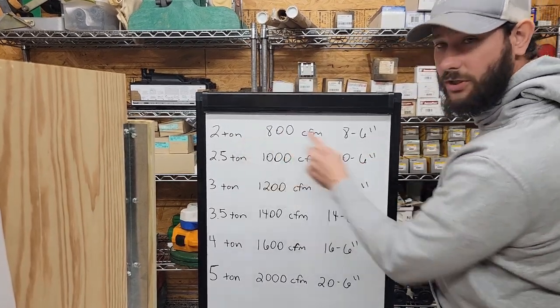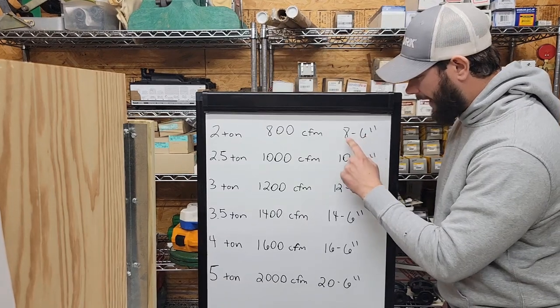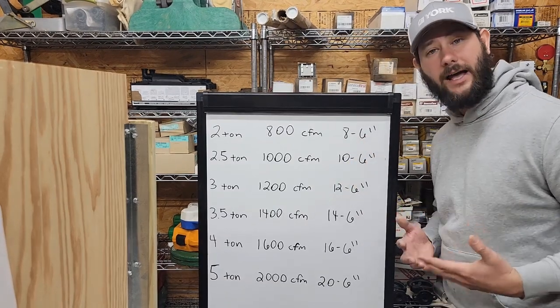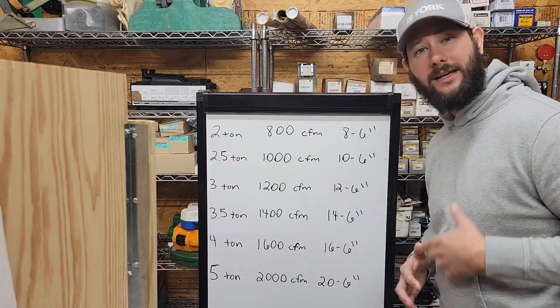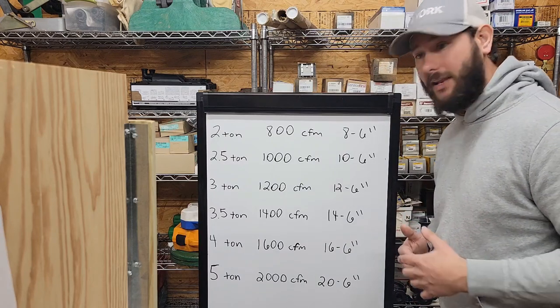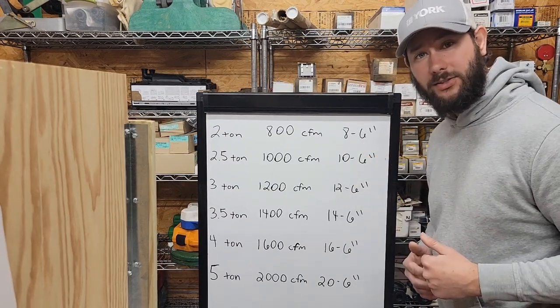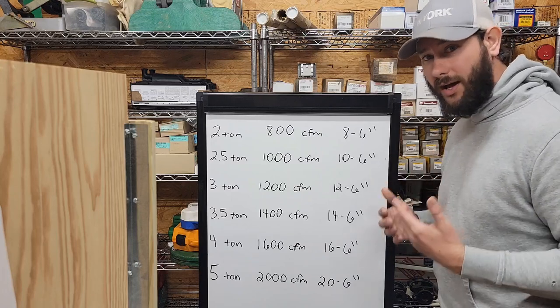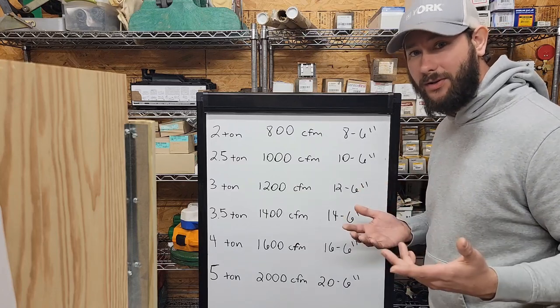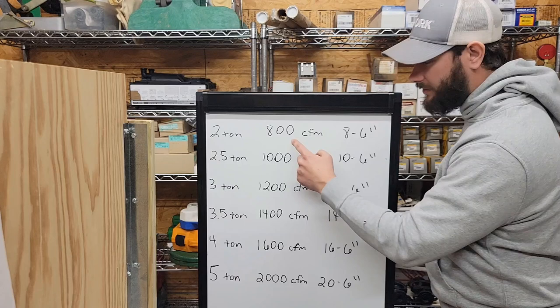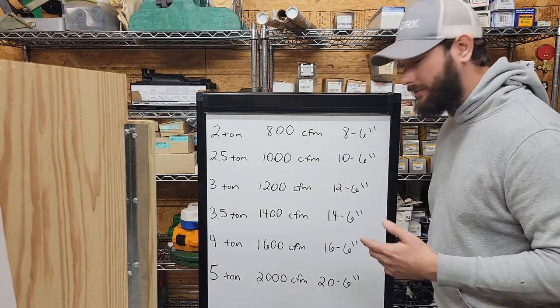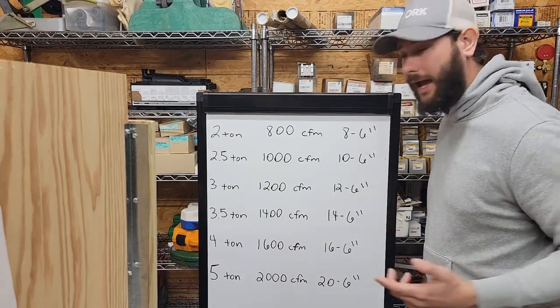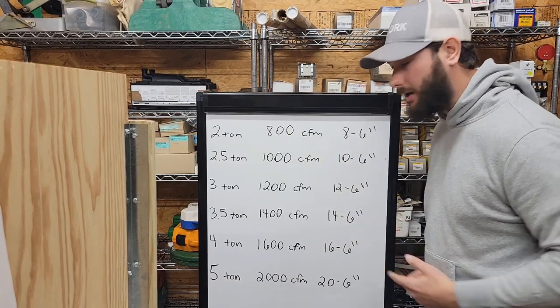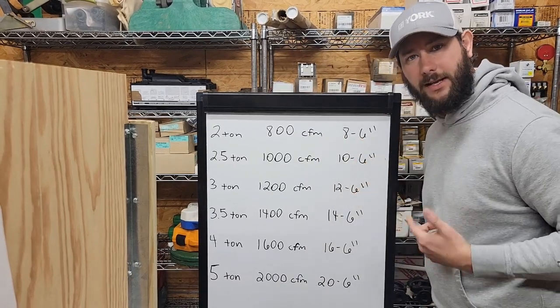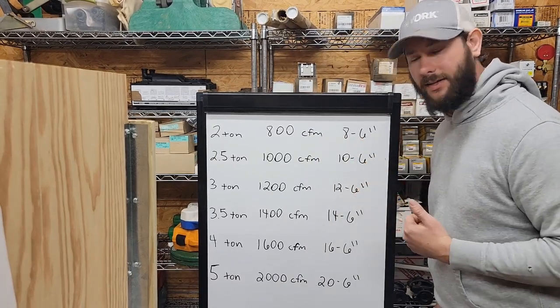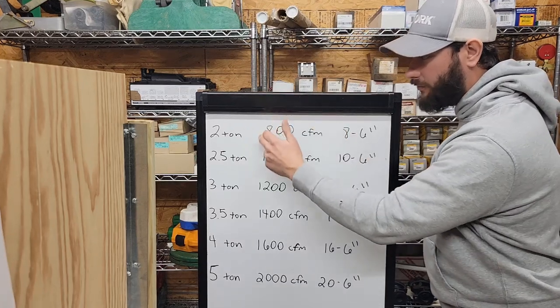When I have a 2-ton unit, I expect to have eight 6-inch lines, because I know that one 6-inch line is about 100 CFM. Eight 6-inch lines times 100 means it's 800 CFM total. So if I have over eight 6-inch lines, I'm going to have over my CFM, or my air quantity.